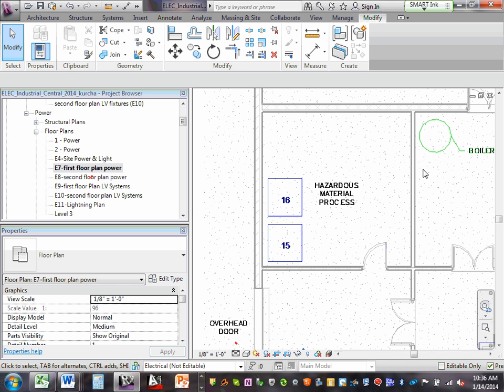Let me ask you a question or two. I don't know what your criteria are here. You call it a hazardous material area. Is the room rated? It's Class 1, Div 1, so explosion proof. So everything that goes inside that room has to be in rigid conduit, seal tight, with no potential for electrical arc. Right?